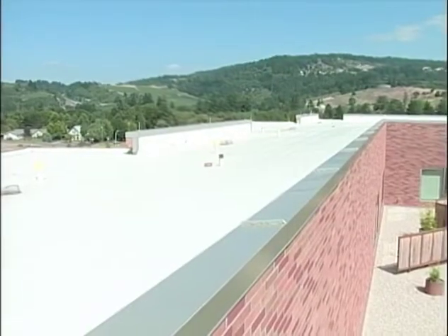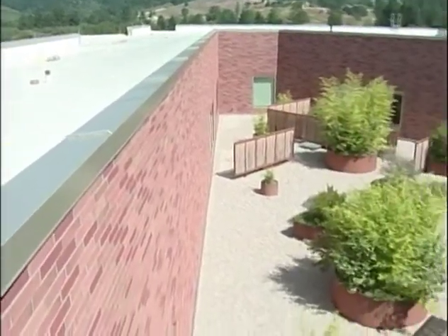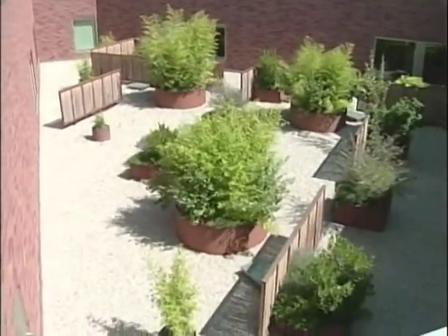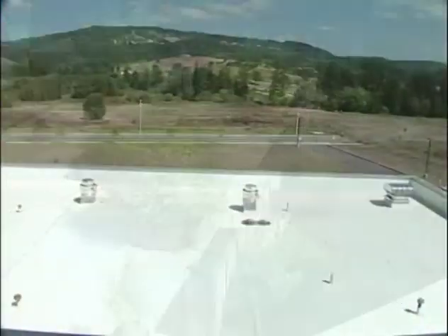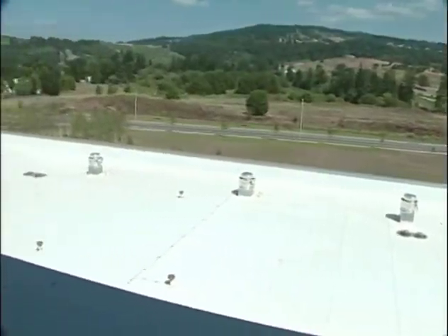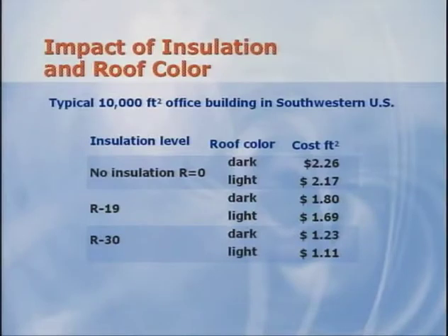Looking at the same office building in the Southwest, notice how insulation and roof color can also have a significant impact on the energy cost of a building. Simply adding insulation and choosing a lighter shade for the roof can reduce energy use. Again, using our office building example, we see that adding additional insulation and choosing a lighter color going up to R30 reduces costs more than 30% over a typical black roof with R19 insulation.